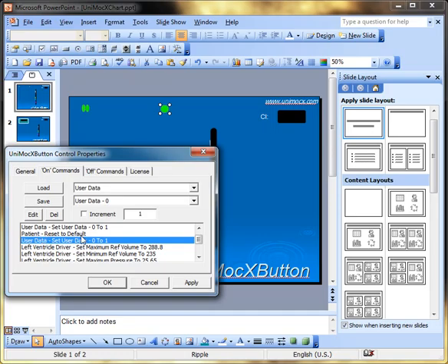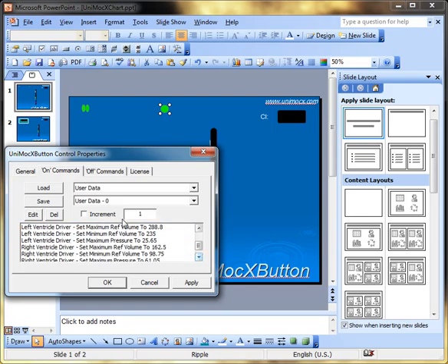Then we go ahead and turn off all those user data, we zero all the user data. Now we reset it, and so this is so that the simulator will actually return the proper value so that the button will know it's on. And we go ahead and we have different reference volumes, etc. that we set to make the simulator behave as if we have an ill patient, and those you can see in the UMExplorer demonstration video.